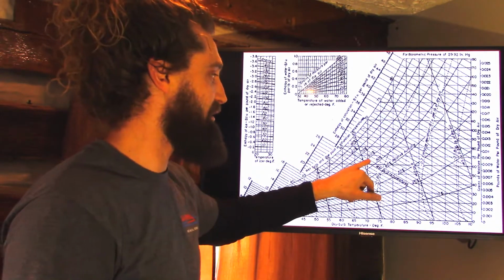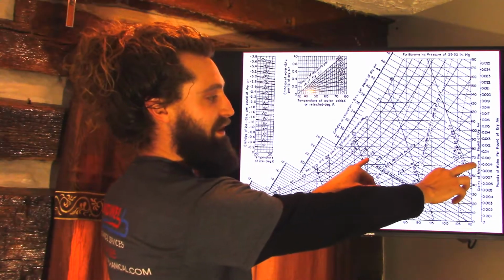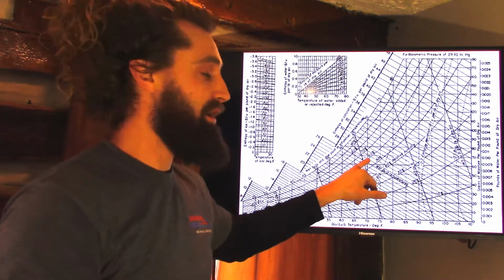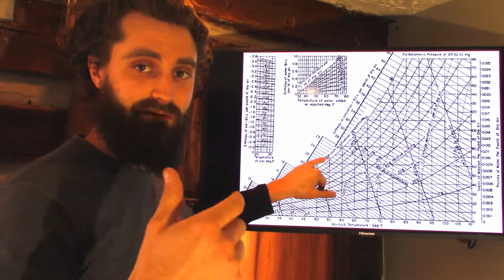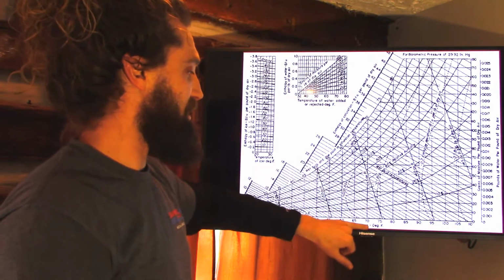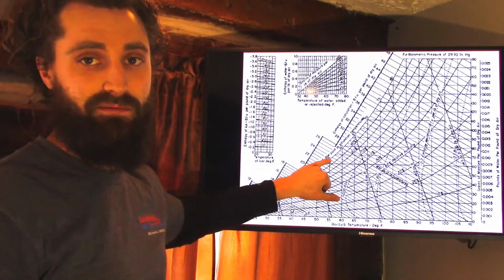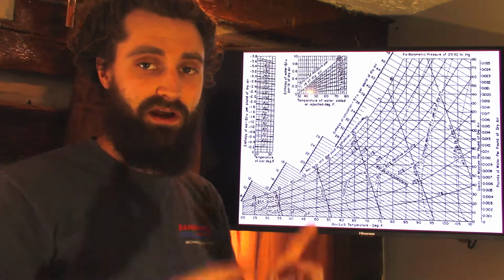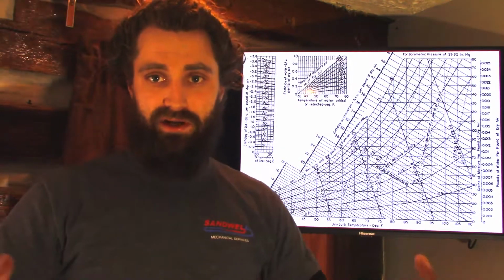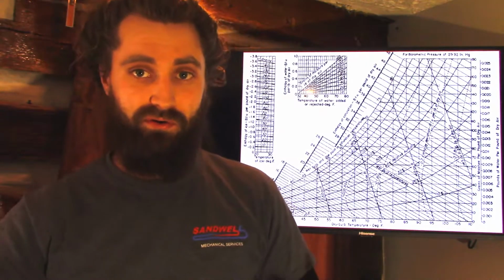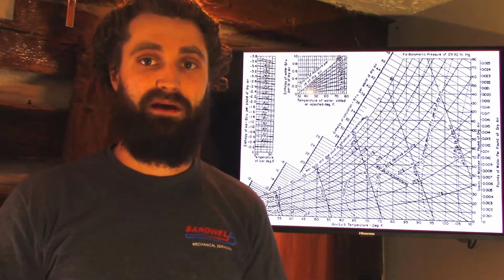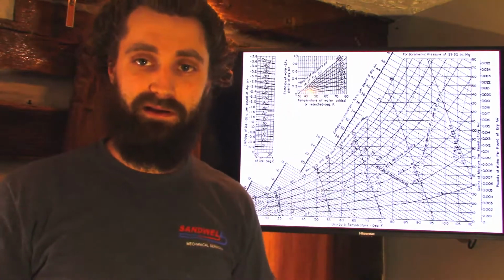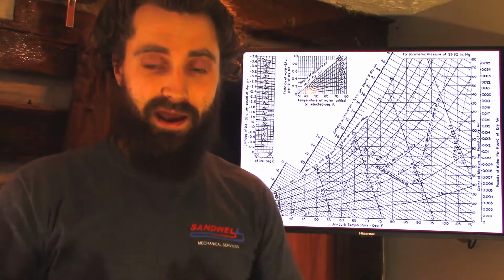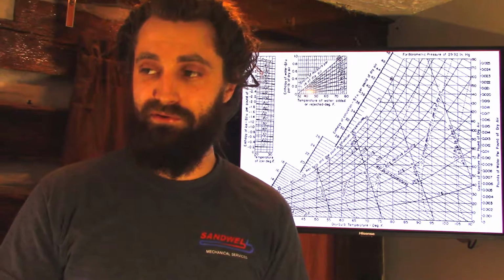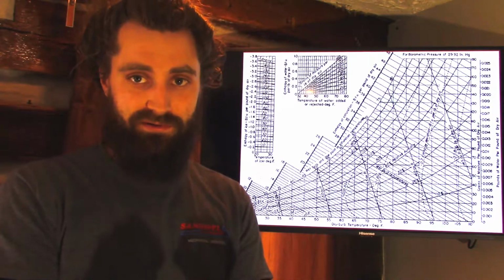Let's say we're getting up to 60%. We can look horizontally to the right to see how many grains of moisture are in the air per pound, or look to the left to find our dew point. At 70 degrees, 60%, our dew point is going to be somewhere around 55 degrees. So any object in your house that is 55 degrees or colder has the potential for condensation to form on it whenever we're up to that 60% humidity. That's an issue, because now we're talking about mold, mildew, stink, and rotting away windowsills. So we don't want too big of a humidifier in a house.